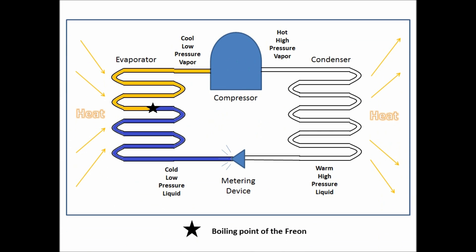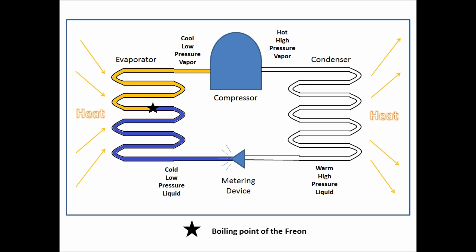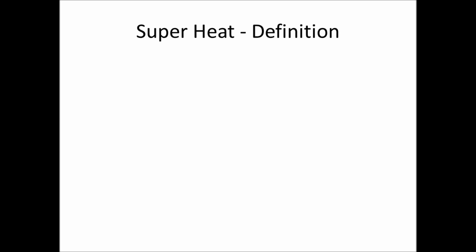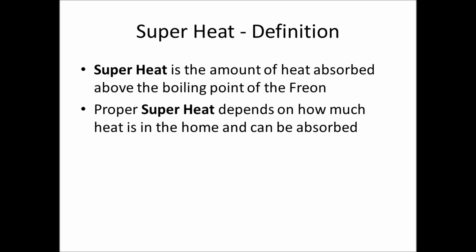On the evaporator side of the refrigeration cycle, the freon enters the evaporator coil — represented here in blue as a liquid freon. At the star point it boils, and the orange represents the vapor of the freon. Superheat is the amount of heat absorbed above the boiling point of the freon — so that's after the star point.